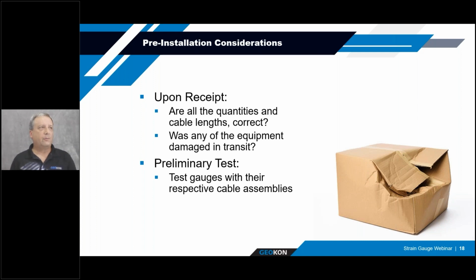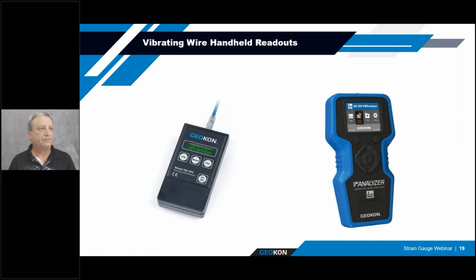Another thing to do before installation, maybe right after you receive these, is a pre-installation acceptance test where you connect your instruments to a handheld readout device to make sure you're getting readings. You can also apply a little force to the ends of the strain gauges to see the changes in conditions and make sure they're responding. If these things aren't working when you receive them, give us a call so we can make it right before you get out to the site.